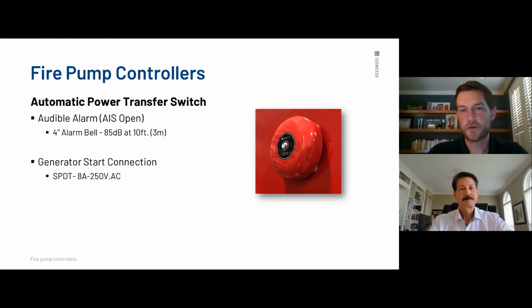There is an audible alarm on the generator side if the isolation switch is open, meaning you haven't turned the power on the transfer switch side. People ask about that frequently, because if you power on the normal power and you haven't powered on the transfer switch side, that bell is going to continue to ring until you turn the power on. So that's the whole reason for that, is that obviously if the isolation switch is open, you don't have your generator. It's basically not going to do you any good. So we have to have an audible alarm for that isolation switch being open, and then also for the generator start connection as well.